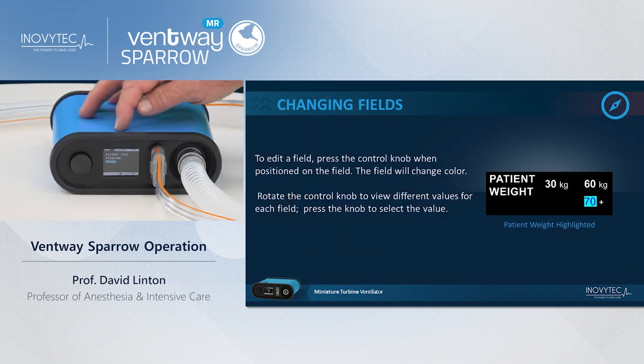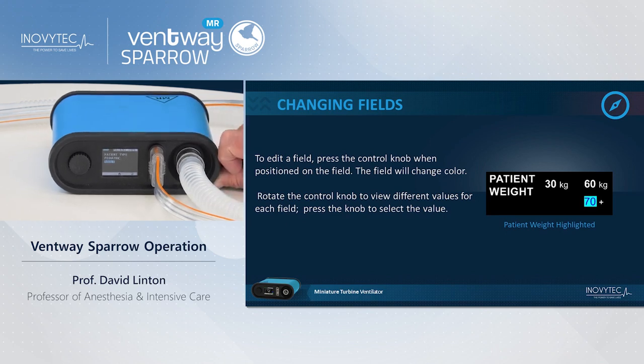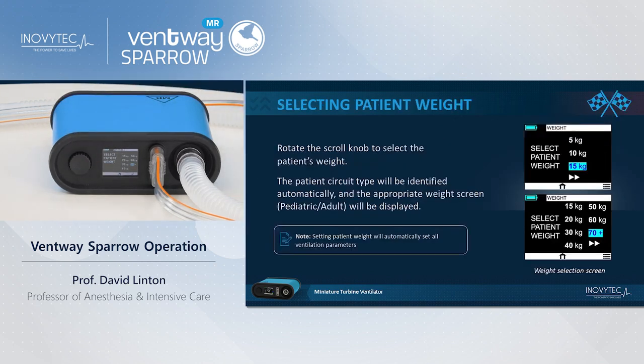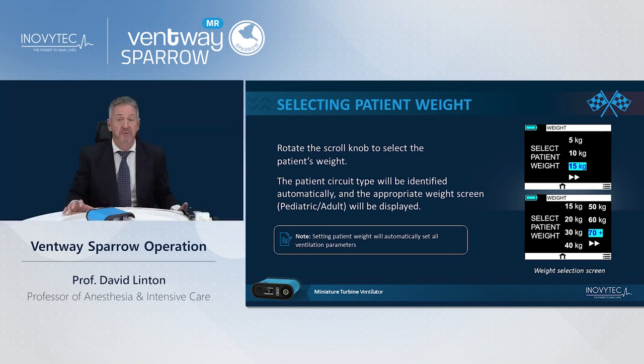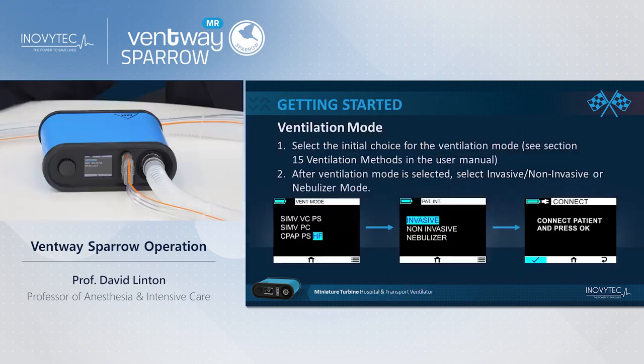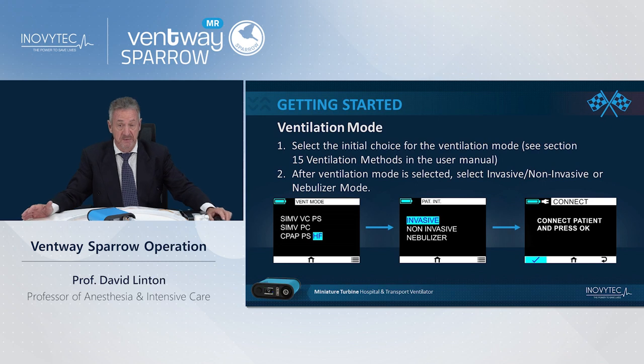The first thing you have to select is whether you want an adult or pediatric ventilator. It automatically starts with pediatric, and all you have to do is click on the button and it will change to pediatric. It then gives you the option to select the patient's weight, because the ventilator has built-in parameters limiting the settings for children and for adults. After you've selected the weight, and in this case with this size lung I'm selecting 60 kilograms, you then have to say which ventilatory mode you want.